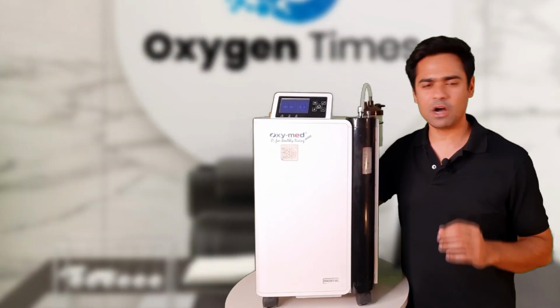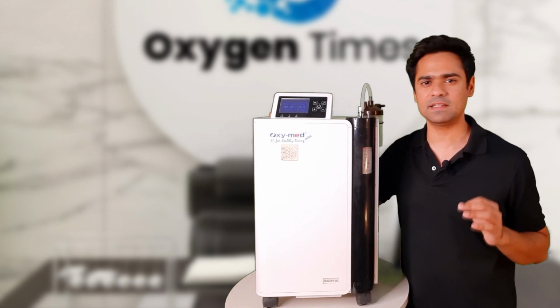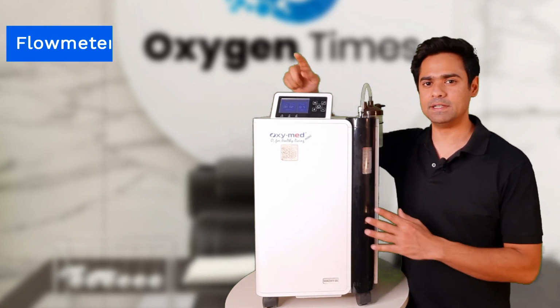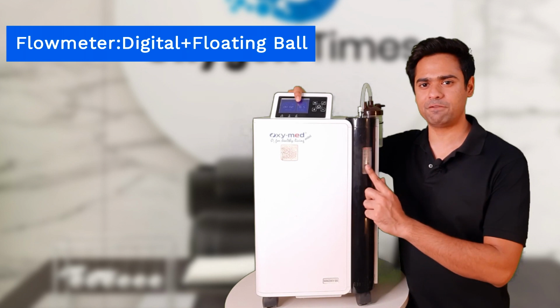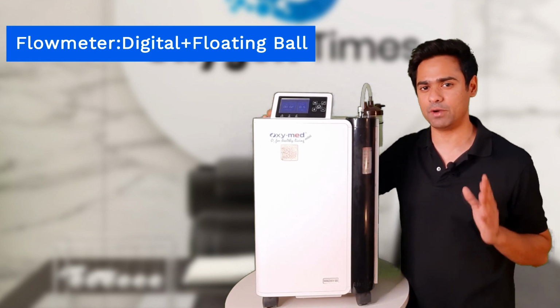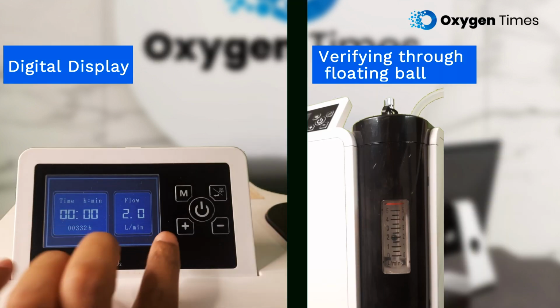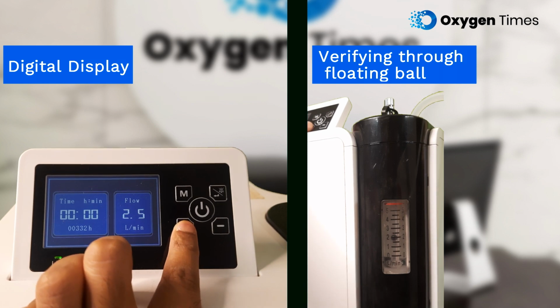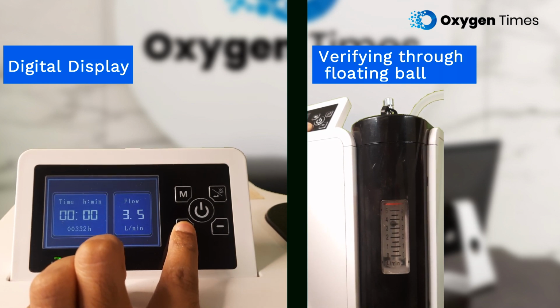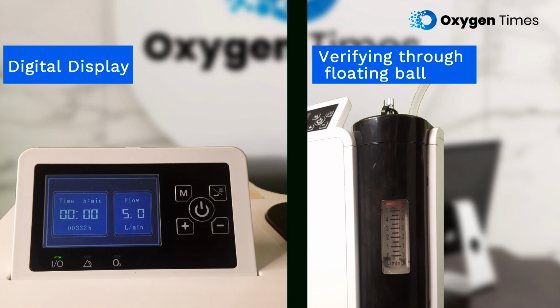Coming to the flowmeter, Oxymed is one of the few companies in the world that have offered both digital and floating ball type flowmeters, both in a single unit. The flow can be set on the digital screen using the plus minus buttons, and the floating ball, located on the right side, gets automatically centered around the flow rate we are setting, making it really easy for you to verify the actual flow being delivered.